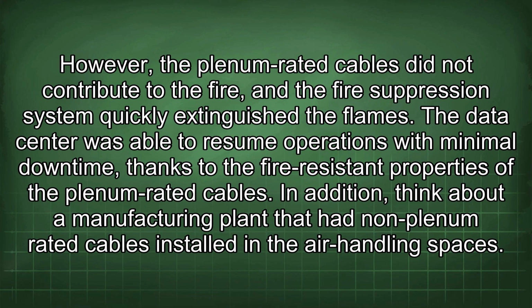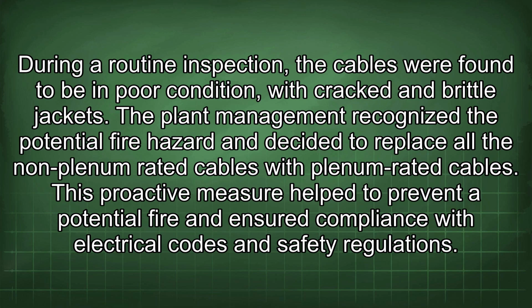In addition, think about a manufacturing plant that had non-plenum-rated cables installed in the air handling spaces. During a routine inspection, the cables were found to be in poor condition, with cracked and brittle jackets. The plant management recognized the potential fire hazard and decided to replace all the non-plenum-rated cables with plenum-rated cables. This proactive measure helped to prevent a potential fire and ensured compliance with electrical codes and safety regulations.